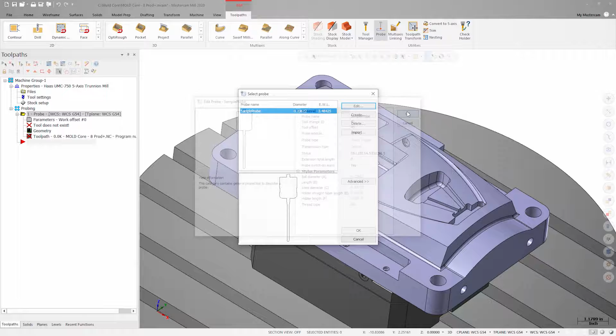We'll be using Productivity Plus, which is the probing add-in for Mastercam. It's located on the Toolpath tab under Utilities. If this is the first time you're creating a probing operation in a file, the Select Probe dialog will open. We'll edit the probe to match Tool 41 on our UMC 750SS, which has a 40+1 capacity tool changer. Once the probe is configured, we can click OK and the probing dialog will open.